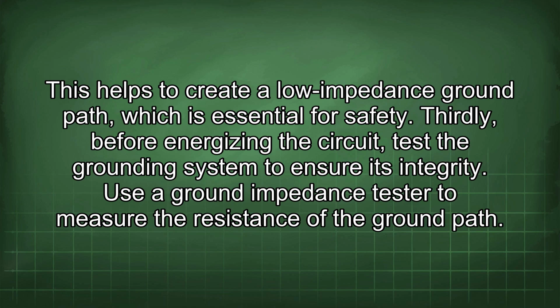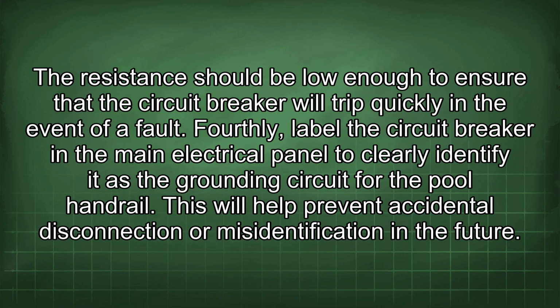Thirdly, before energizing the circuit, test the grounding system to ensure its integrity. Use a ground impedance tester to measure the resistance of the ground path. The resistance should be low enough to ensure that the circuit breaker will trip quickly in the event of a fault. Fourthly, label the circuit breaker in the main electrical panel to clearly identify it as the grounding circuit for the pool handrail. This will help prevent accidental disconnection or misidentification in the future.